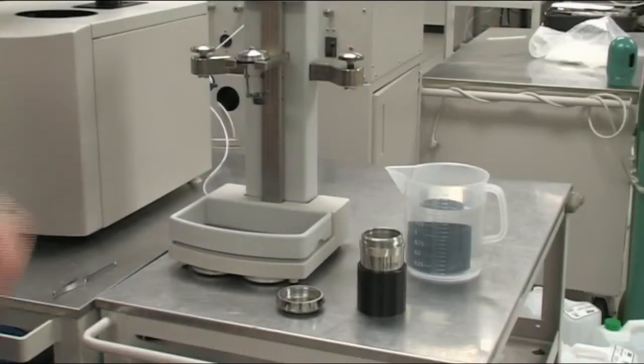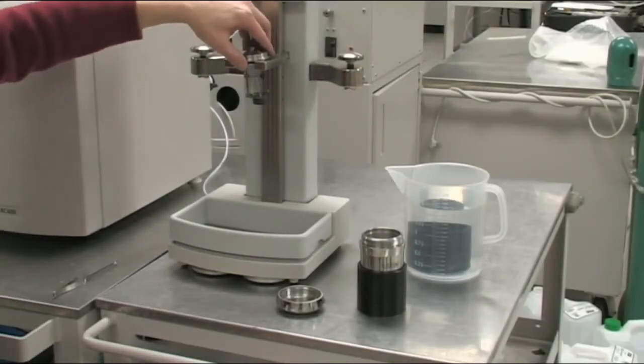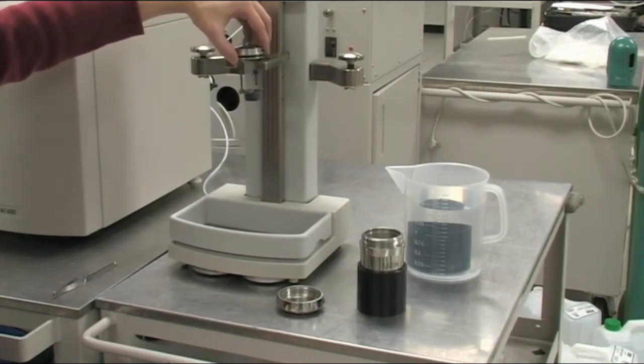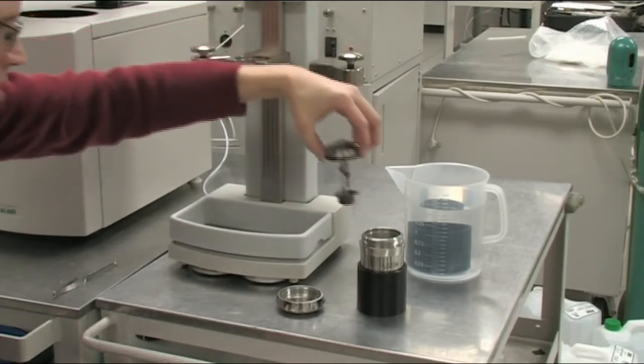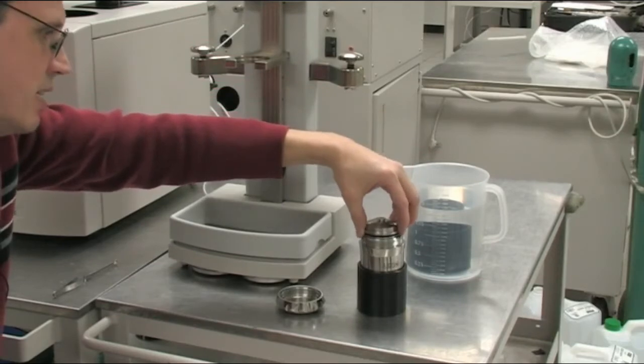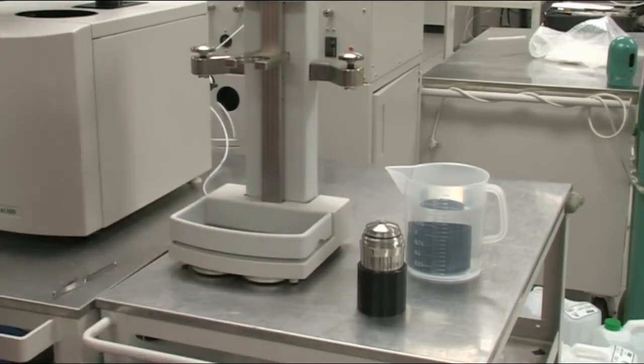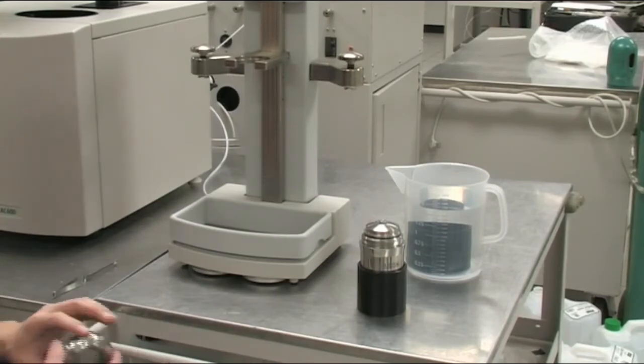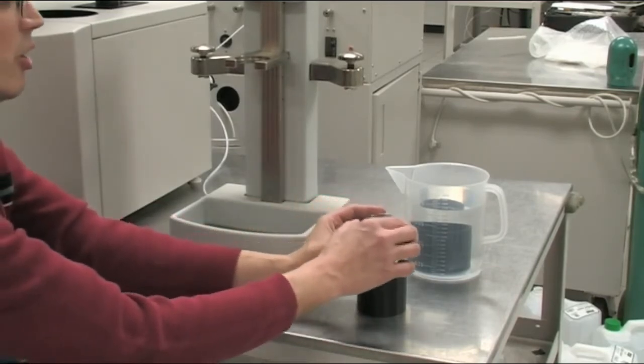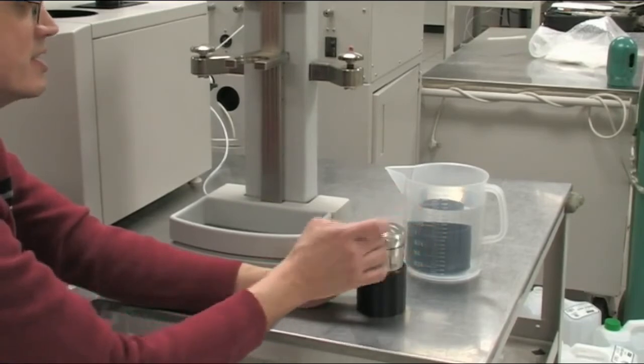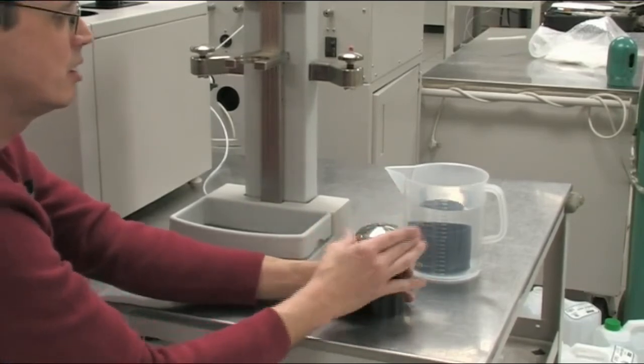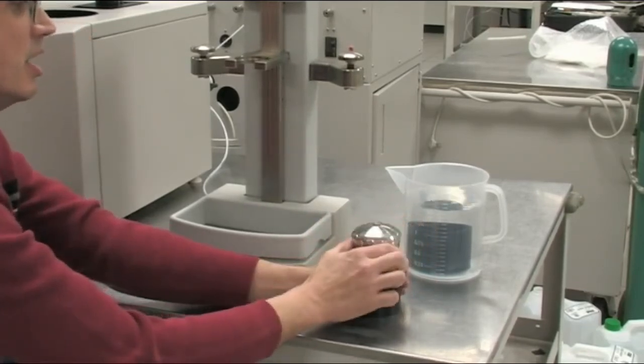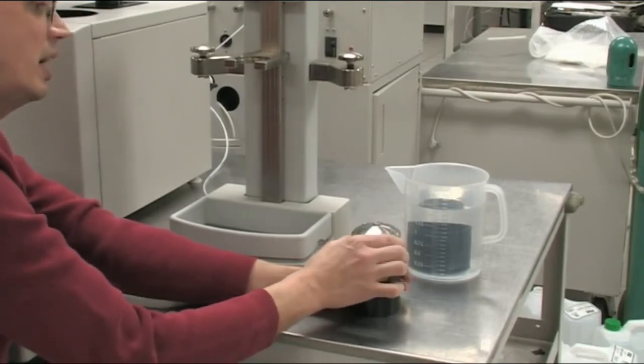You're now ready to put the sample igniter into the combustion vessel. Carefully remove it from the station and place it carefully on the vessel. You don't want to push the igniter down into the vessel because you don't want to nick the O-ring. Nicking the O-ring would be a source of leaks. Hand tighten the ring on the vessel.